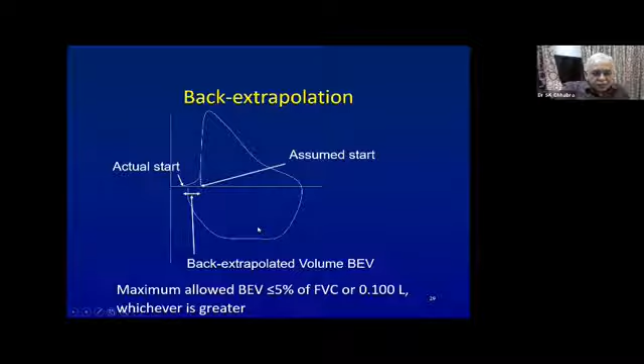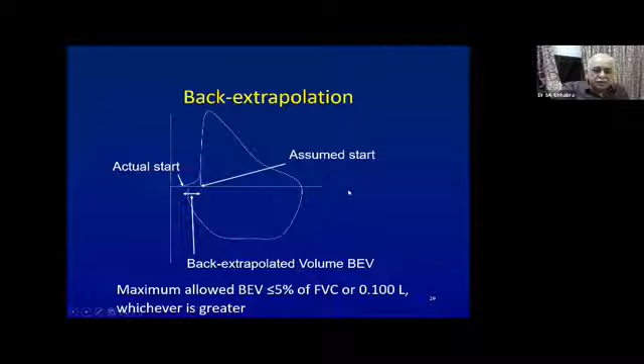So what is done is that we drop a vertical here to the x-axis, and then take this as the starting point. This is the assumed start. So this volume is deleted or subtracted from the forced vital capacity if it is less than 100 ml, because that does not materially alter the results. So this is the back extrapolation volume, and the software will tell you if in this effort the back extrapolation volume was 100 ml or more. If it is 100 ml or less, or 5% of the total vital capacity, then we are okay with this and we accept the effort. Otherwise, this is rejected.